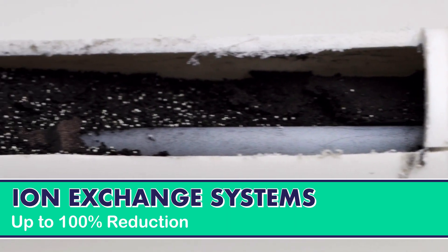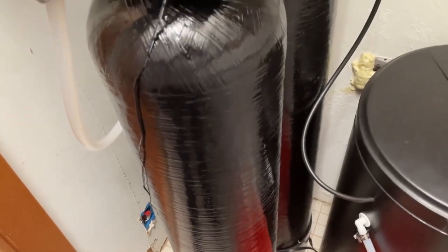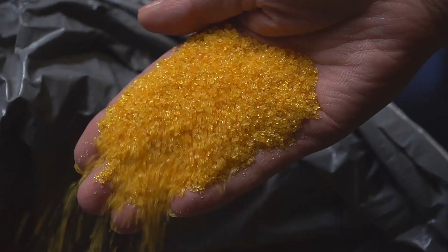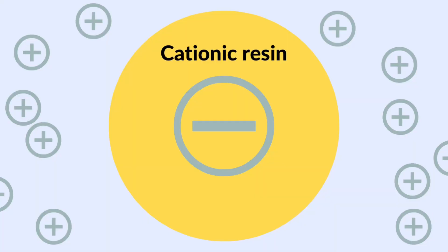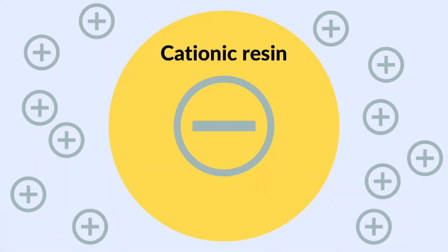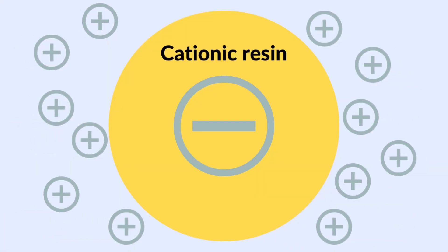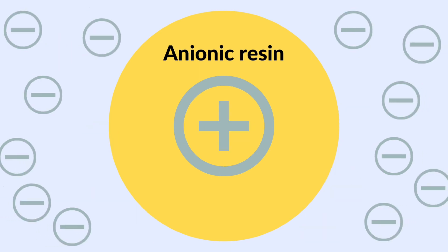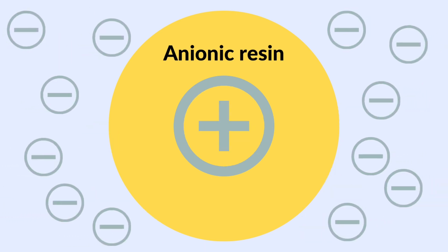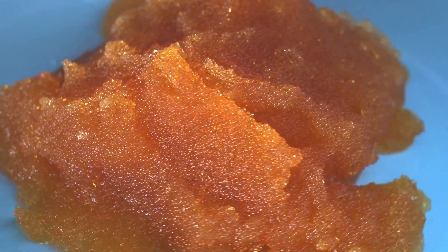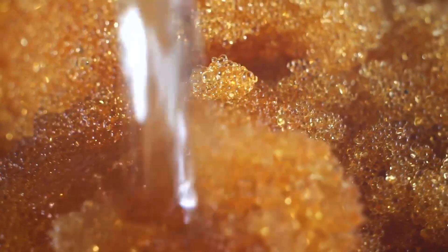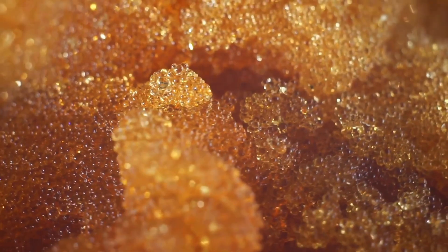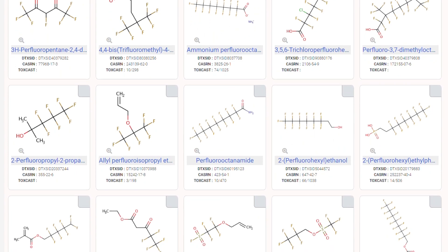Ion exchange systems are another effective solution for removing PFAS. These systems utilize a tank or cartridge filled with an ion exchange resin, either anionic or cationic. Cationic resins are negatively charged and remove positively charged impurities, while anionic resins are positively charged and remove negatively charged impurities. Acting like magnets, these resins attract specific contaminants, preventing them from passing through the system along with water particles. Anionic resins are the best choice for removing PFAS, since these chemicals are typically negatively charged.